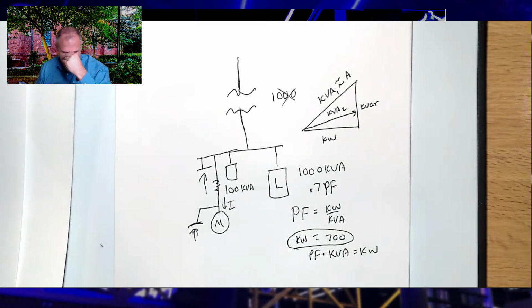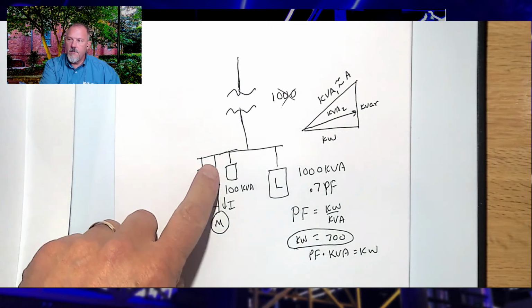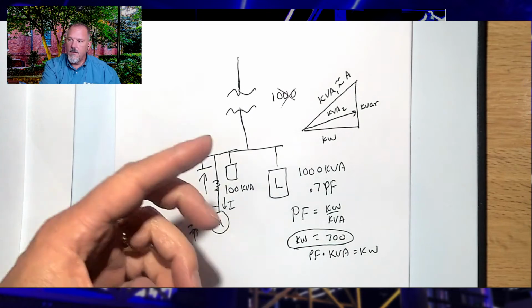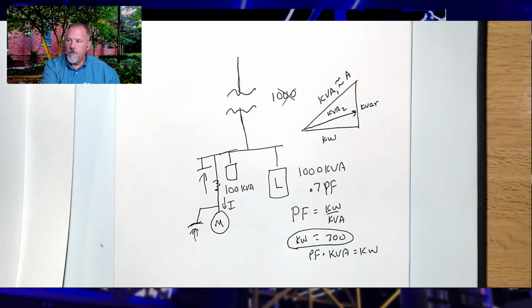So anyway, it was a high-rise building, and they were using around 1,500 kilowatts of load, and by doing power factor correction, even out at the very end of the HVAC units and all the motors and stuff like that, if we exaggerated it, we could probably get around 2%, maybe 3% savings at the very most, right? And that's really just because of those I squared R losses, the resistance of those lines. Even if it's 400 feet away, it's just not that much.